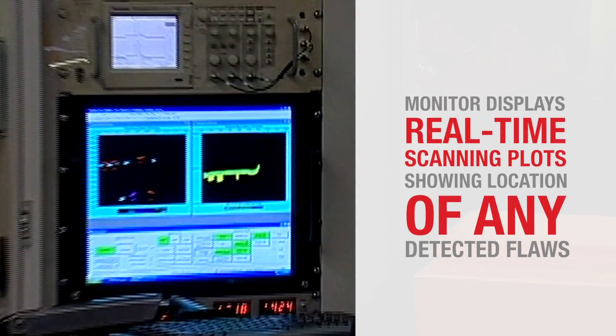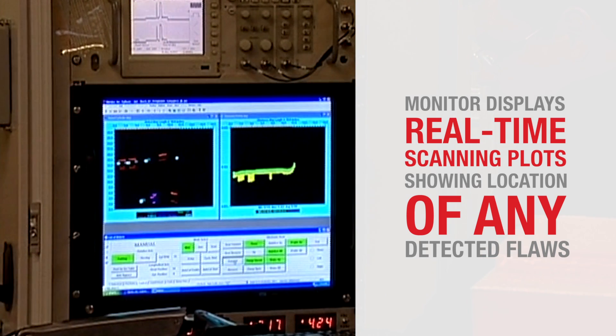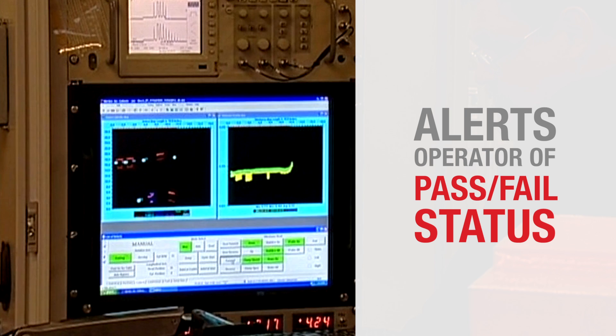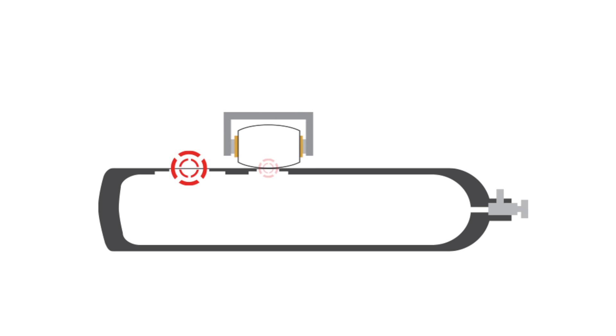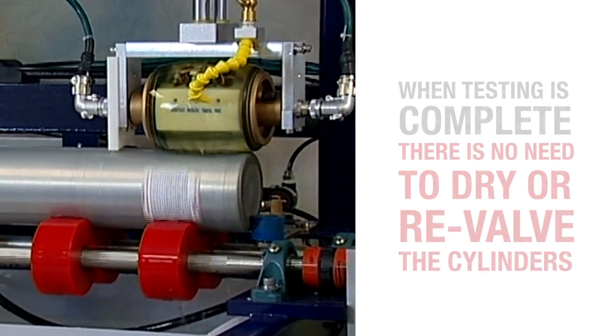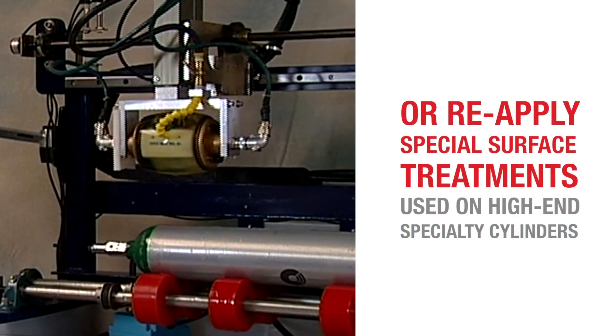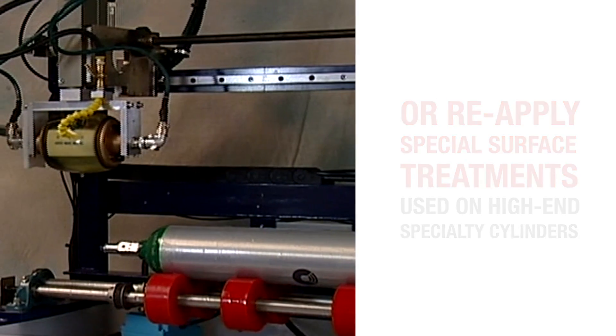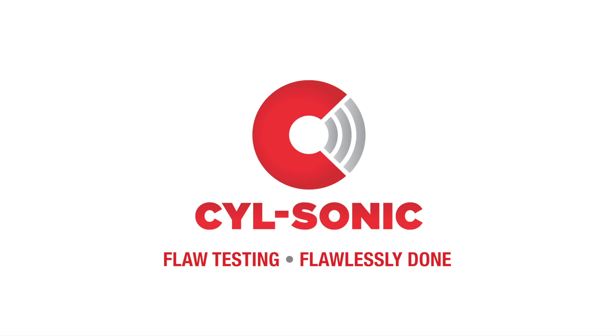The monitor displays real-time scanning plots, showing the locations of any detected flaws. The system also alerts the operator about the cylinder's pass-fail status. For example, if the wall thickness falls below the established minimum at any point, the cylinder is automatically marked as failed. When the testing is complete, there is no need to dry or revalve the cylinders, nor any need to reapply special surface treatments used on high-end specialty gas cylinders. This means your production levels are much higher than with hydrostatic methods. Cyl-Sonic — flaw testing, flawlessly done.